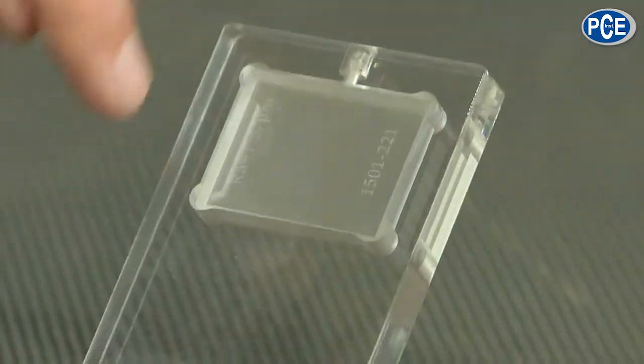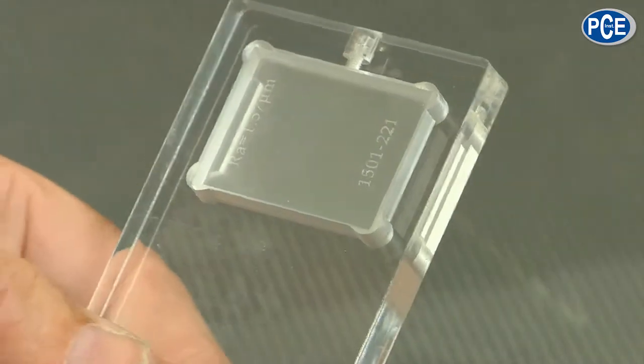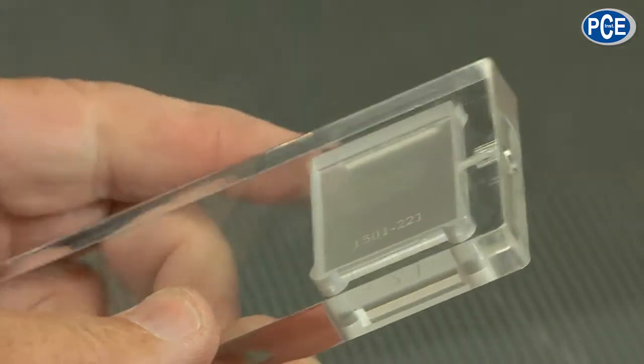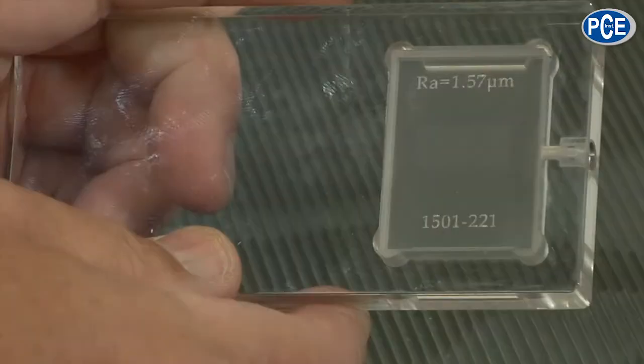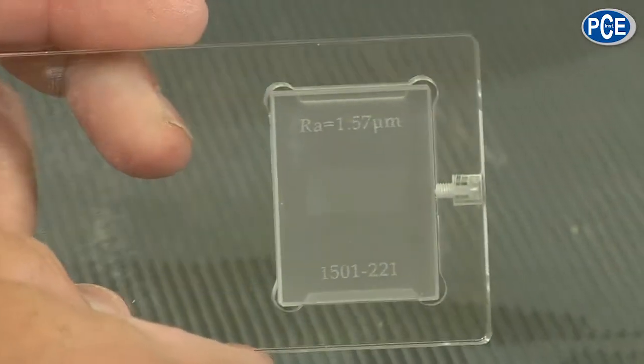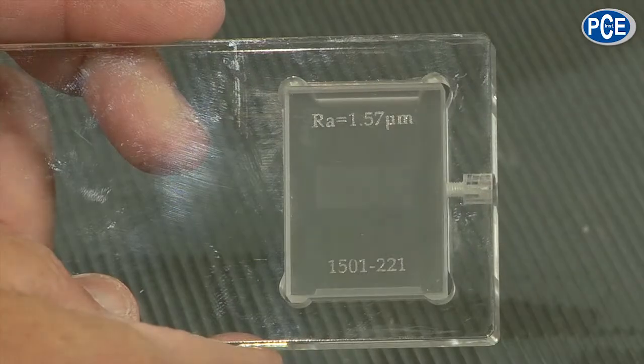So this is delivered with it. This is a calibration probe. That is this piece. You should try not to touch it and not polish or whatever. And on its stand, I don't know if you can see that in the camera, what the device should show: 1.57 micrometer when you're standing on it.